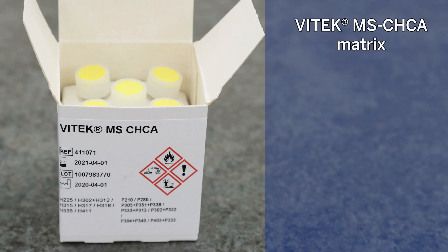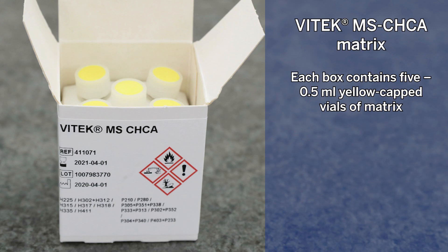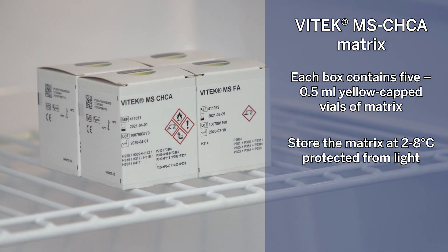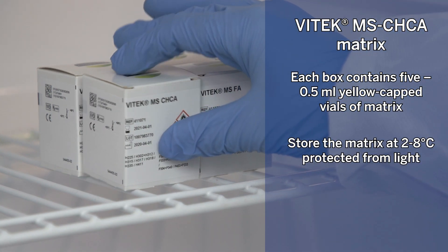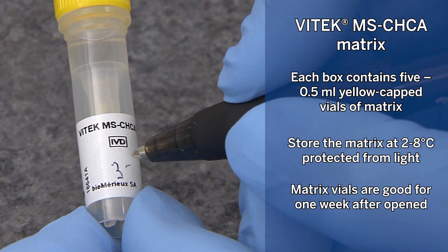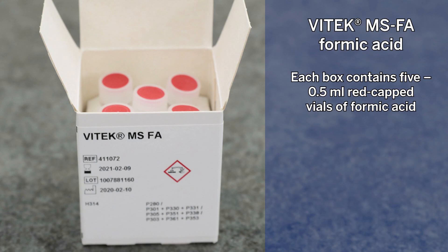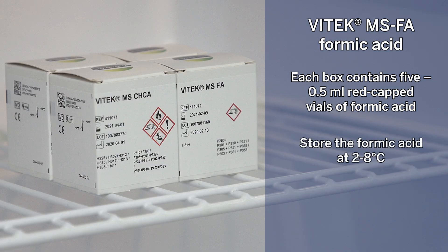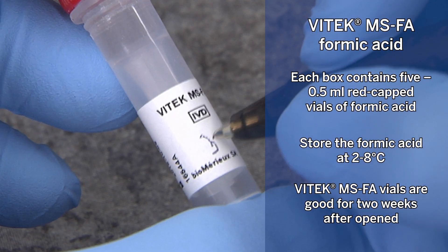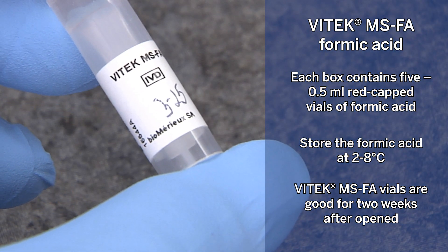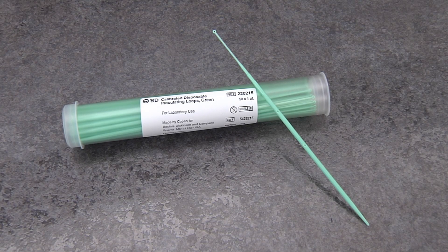Vitek-MS CHCA matrix: each box contains 5 vials of 0.5 milliliter yellow-capped matrix. Store the matrix at 2 to 8 degrees Celsius protected from light. Matrix vials are good for one week after opened. Vitek-MS FA formic acid: each box contains 5 vials of 0.5 milliliter red-capped formic acid. Store the formic acid at 2 to 8 degrees Celsius. Formic acid vials are good for two weeks after opened. Also needed: 1-microliter calibrated loops and precision pipetters to deliver 0.5 and 1 microliter.